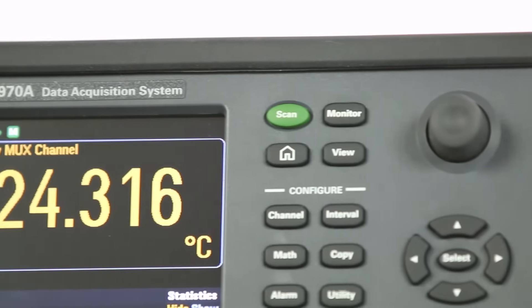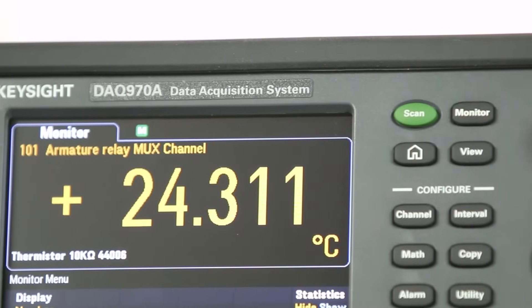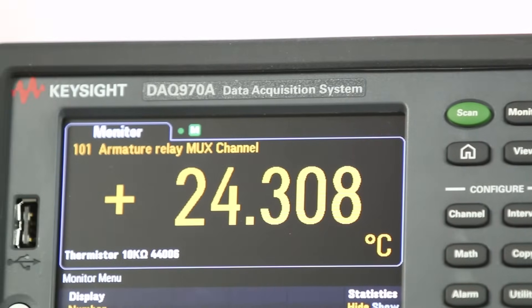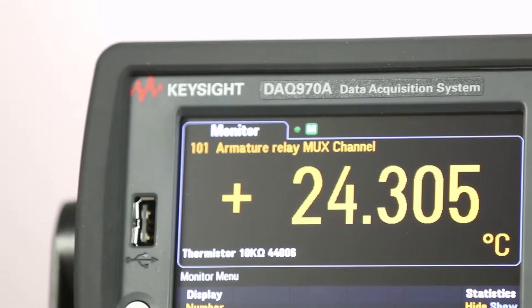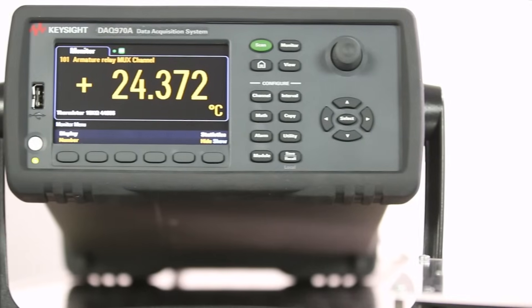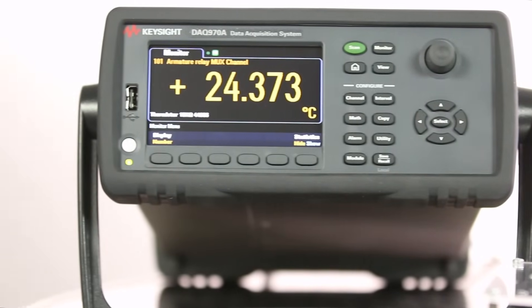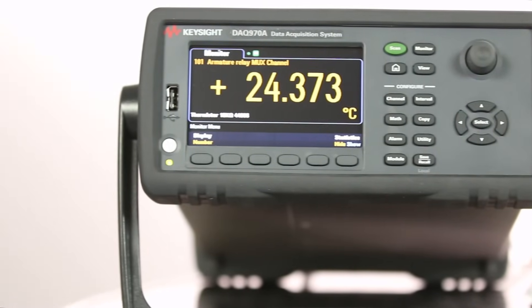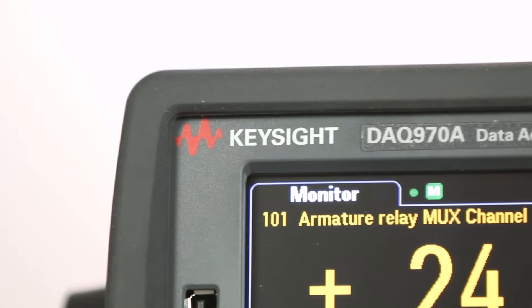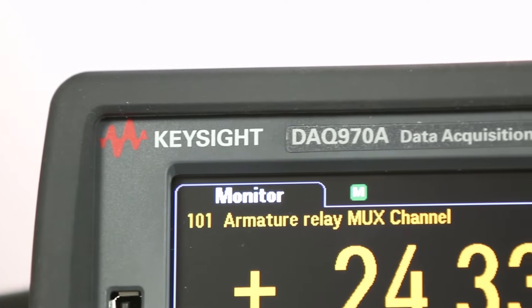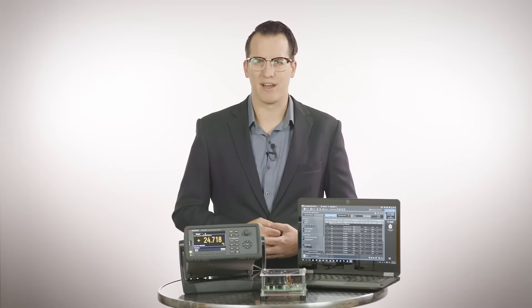This generation, the DAQ 970A, builds on the proven design of the 34970A and 34972A. The DAQ 970A mainframe has a built-in advanced 6.5-digit DMM and signal conditioning that speeds up test development time.